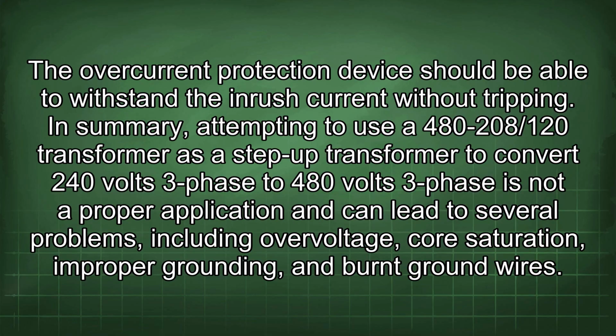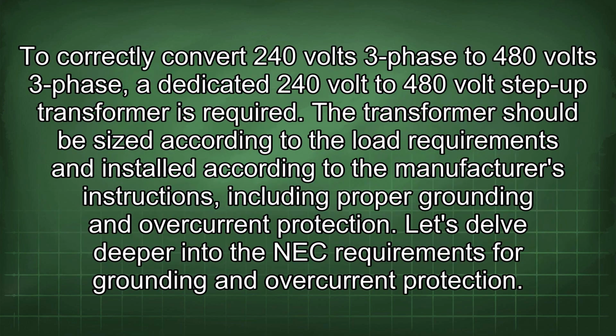In summary, attempting to use a 480-208/120 transformer as a step-up transformer to convert 240 volts 3-phase to 480 volts 3-phase is not a proper application and can lead to several problems, including overvoltage, core saturation, improper grounding, and burnt ground wires. To correctly convert 240 volts 3-phase to 480 volts 3-phase, a dedicated 240 volt to 480 volt step-up transformer is required. The transformer should be sized according to the load requirements and installed according to the manufacturer's instructions, including proper grounding and overcurrent protection. Let's delve deeper into the NEC requirements for grounding and overcurrent protection.